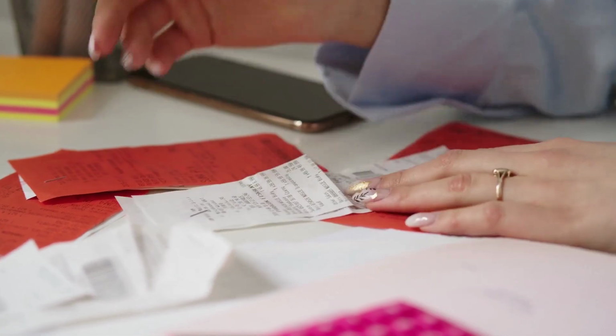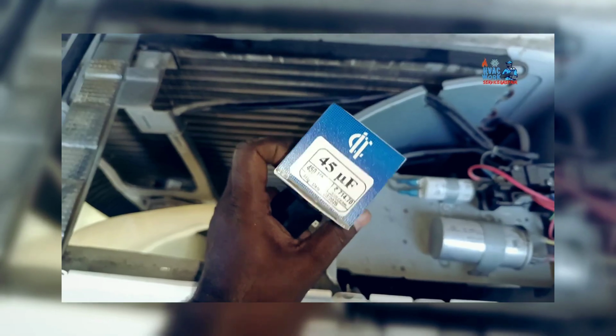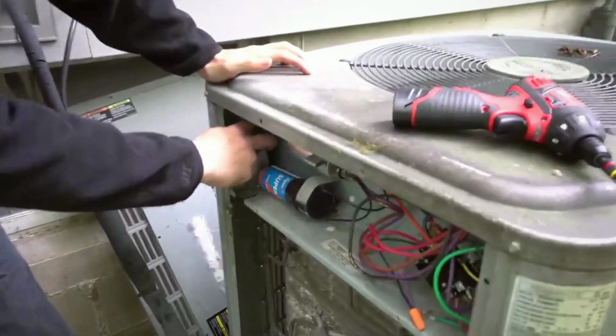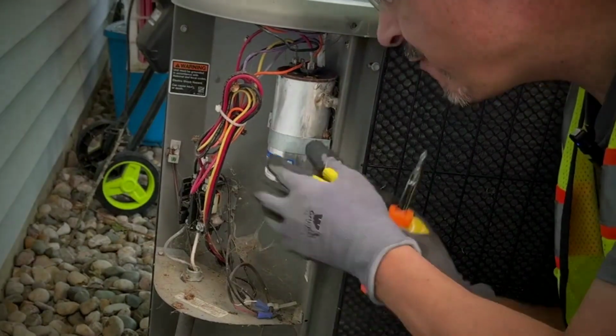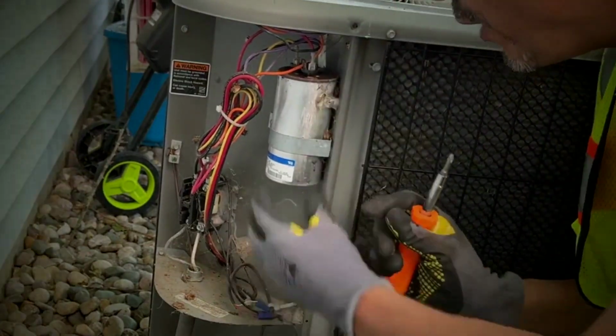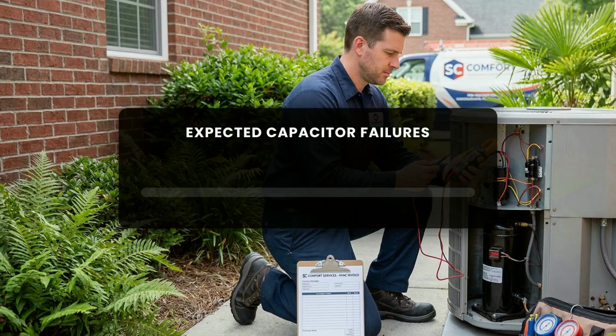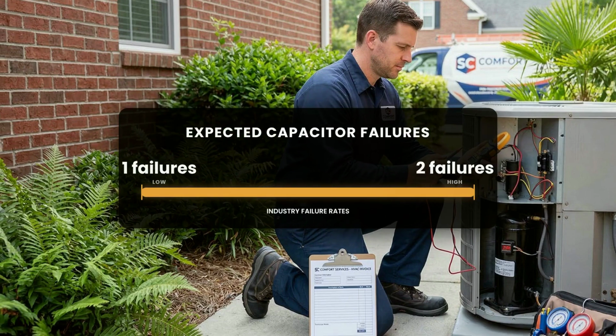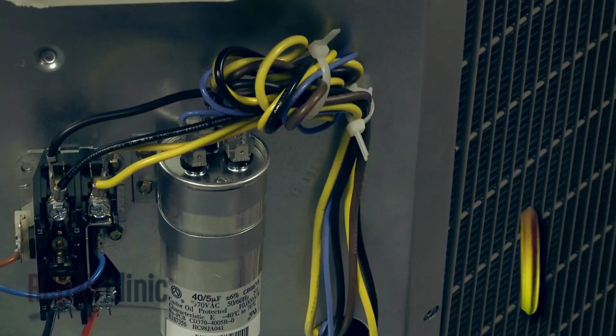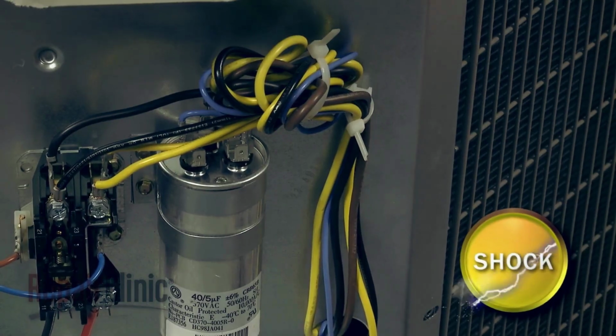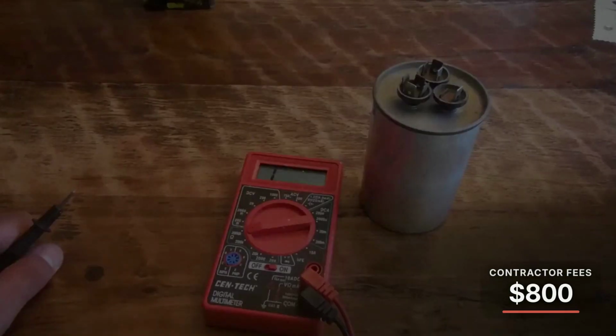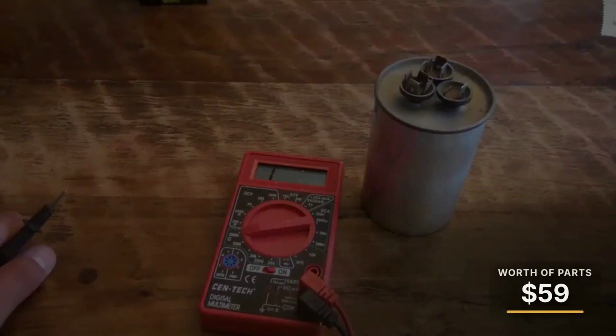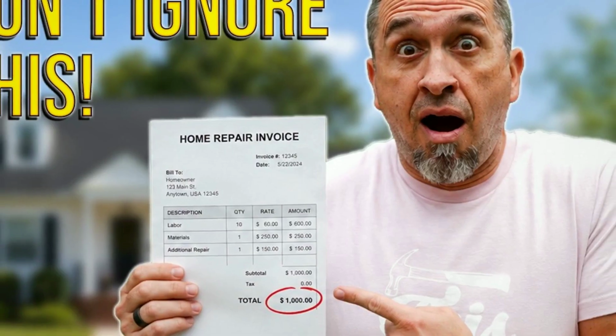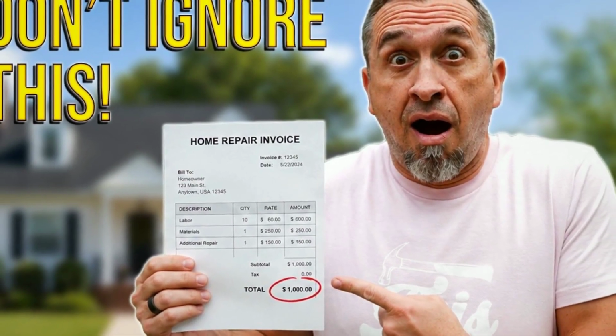But this subject wasn't done yet. Not even close. Run the 10-year math and the picture gets worse. If your system is a decade old, industry failure rates suggest you will face 1 to 2 capacitor failures over the next 10 years. At $400 per service call, that is $800 in contractor fees for what amounts to $60 worth of parts. $60. That's the kind of number that makes accountants cry. The clock was already ticking. Your system just couldn't hear it yet.